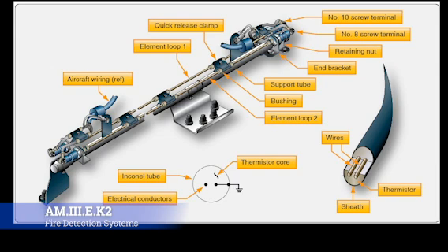Now, the best advantage is that it offers complete coverage over the fire zones. It resists damage from vibration. It's really robust and will resist oil, water, extreme temperatures. It doesn't weigh anything. It gives you pretty accurate results pretty quickly, and it's really good for fault indication for shorts. And it doesn't rely on rate of heat rise like the Fenwal system does. It's pretty simple, pretty robust in the middle of it all.